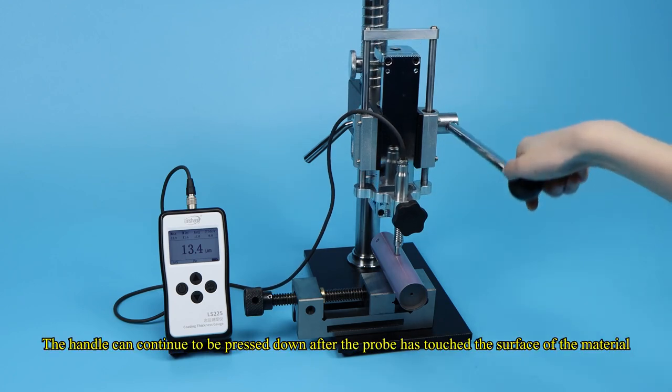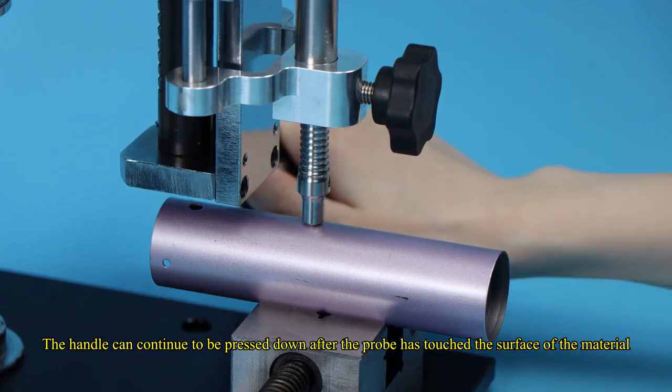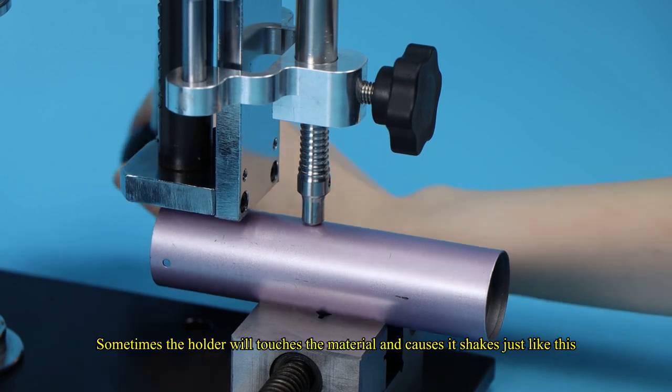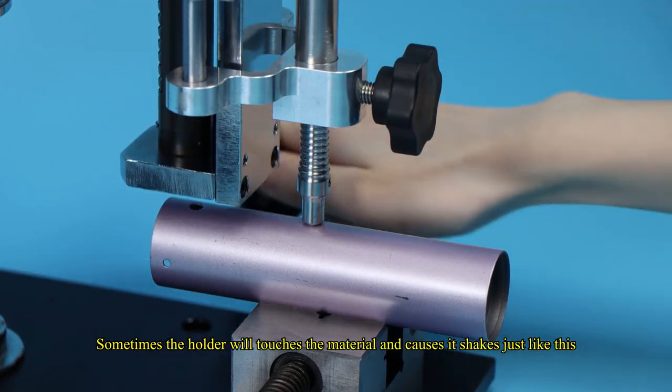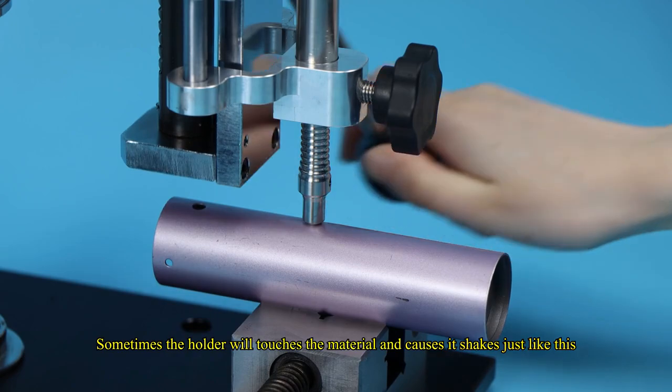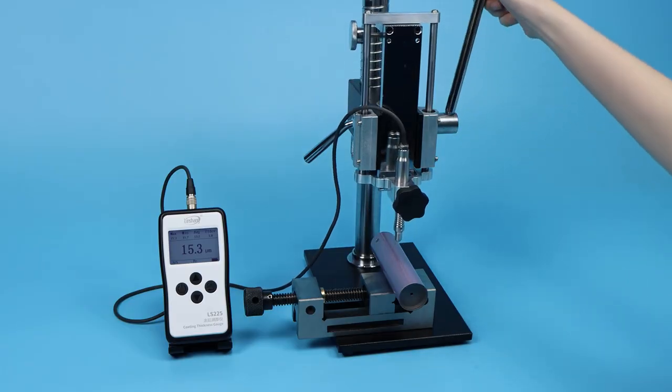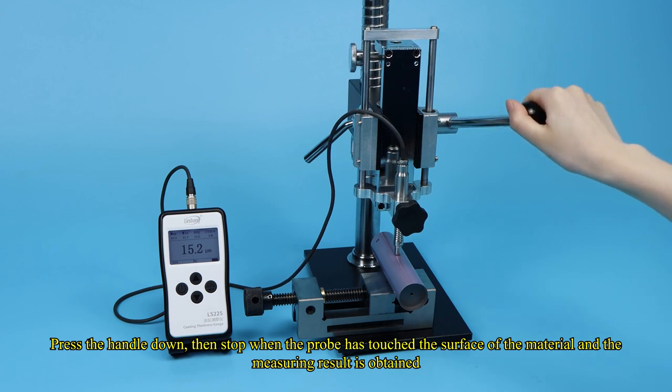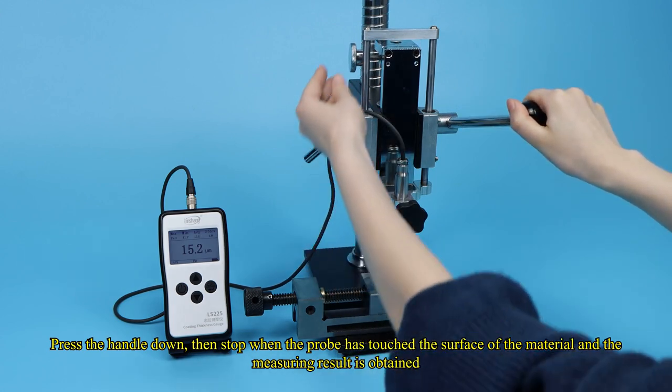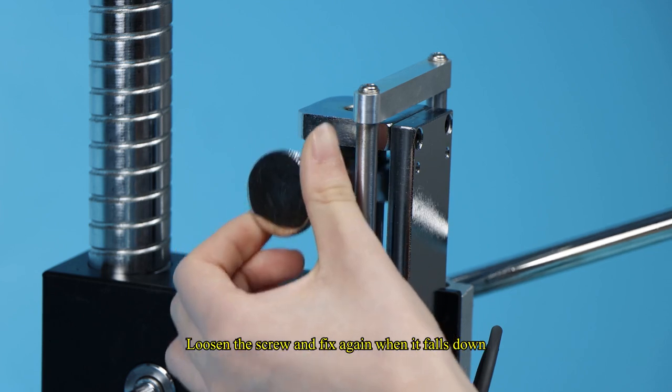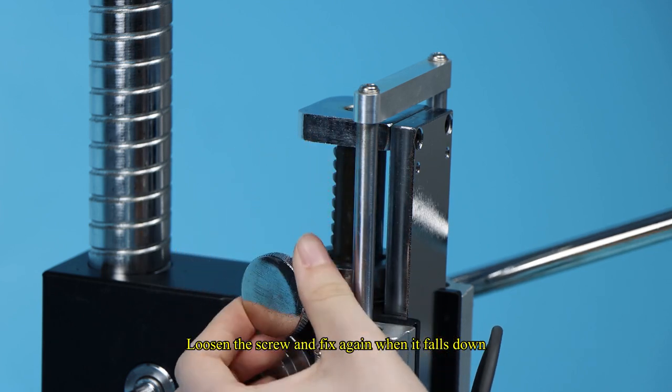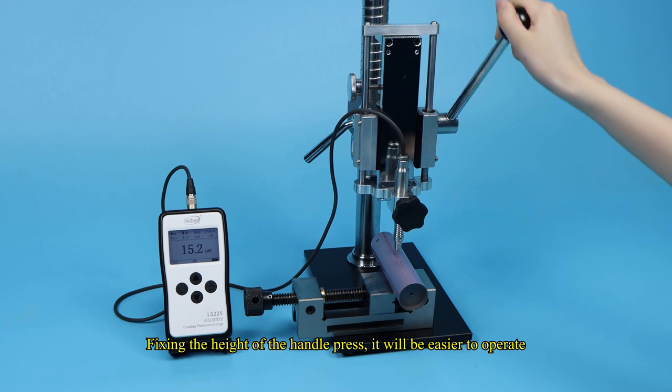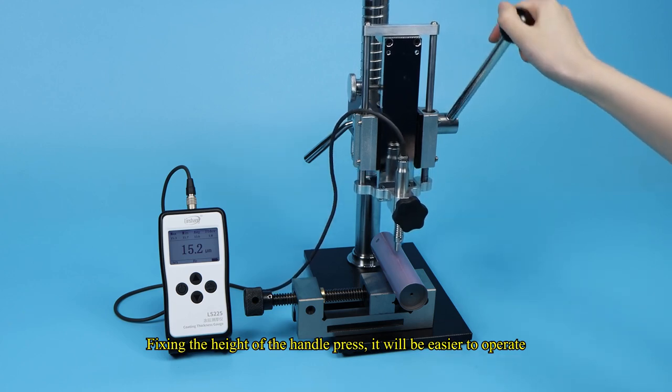The handle can continue to be pressed down after the probe has touched the surface of the material. Sometimes the holder will touch the material and cause it to shake just like this. Press the handle down, then stop when the probe has touched the surface of the material and the measuring result is obtained. Loosen the screw and fix again when it falls down. Fixing the height of the handle press, it will be easier to operate.